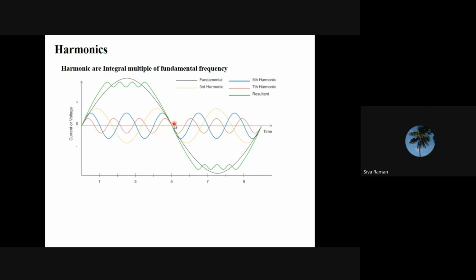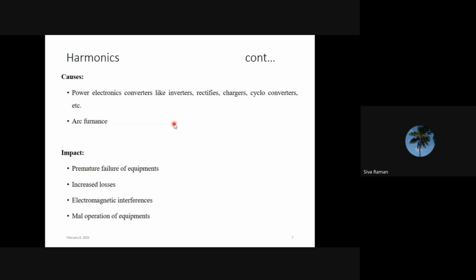So due to that, the equipment may mal-operate. The main reason for the harmonics is mostly the power electronic based equipment like inverters, rectifiers, chargers, and cycloconverters, and arc furnaces. An arc furnace does not come under power electronic based equipment, but it also will produce harmonics.